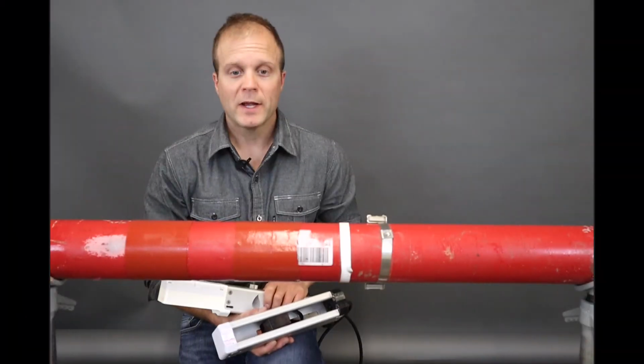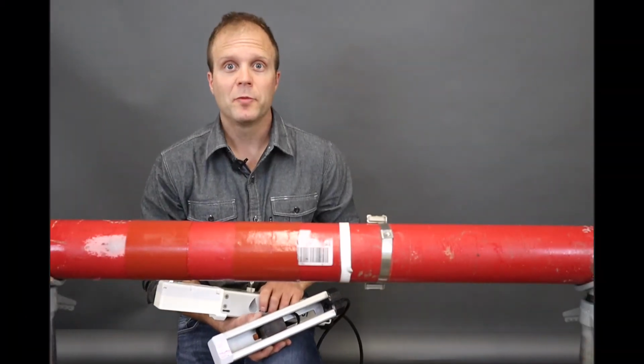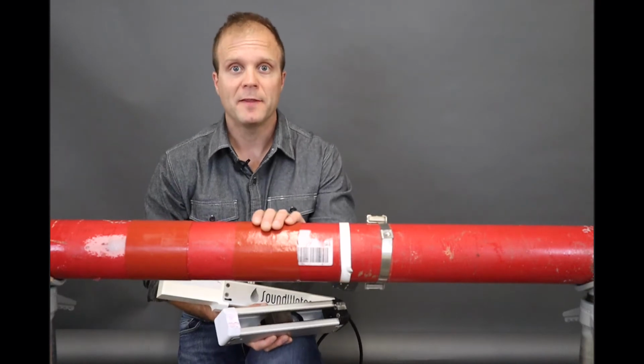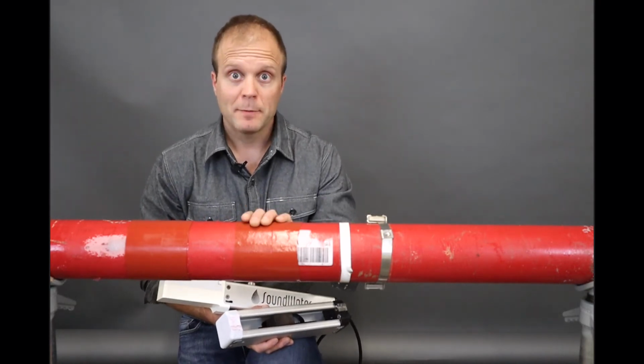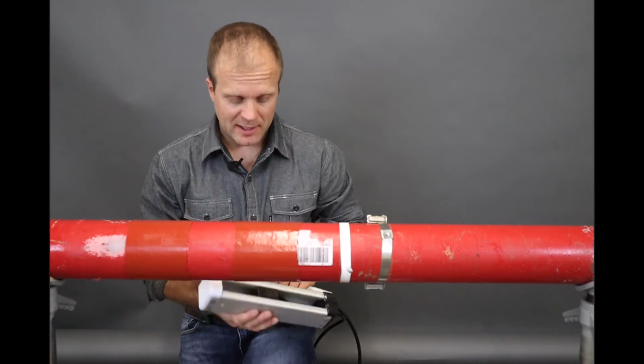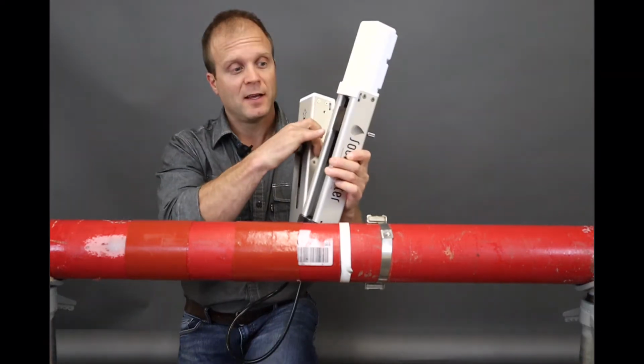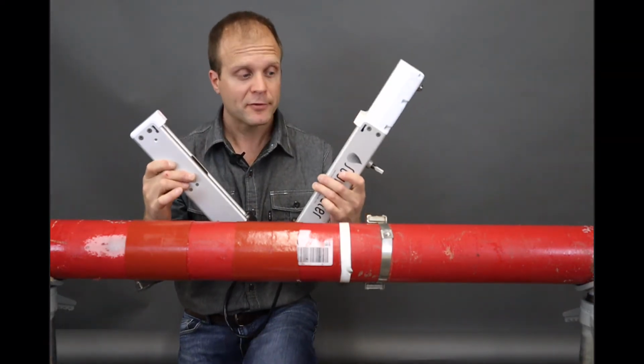We're now ready to put the meter on the pipe. Okay, so now we can install our flow meter on top of the coupling pad that's on the pipe. Your coupling pad should still be clean, as well as the transducer faces in both halves. They must also be very clean.